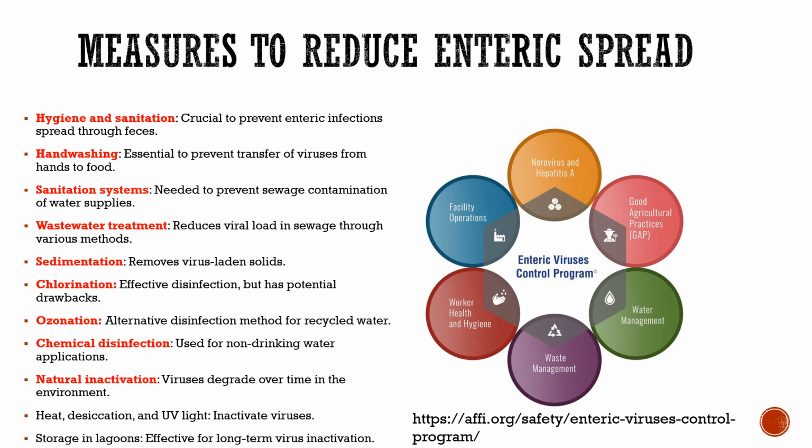In countries where wastewater is recycled for drinking and other domestic purposes, the treated effluent is further treated by coagulation with alum or ferric chloride, adsorption with activated carbon, and finally chlorination. Evidence that byproducts of chlorination are toxic to fish and may be carcinogenic for humans has encouraged several countries to return instead to ozonation. Ozone is a very effective oxidative disinfectant for viruses as well as bacteria, provided that most of the organic matter containing adsorbed viruses is first removed.